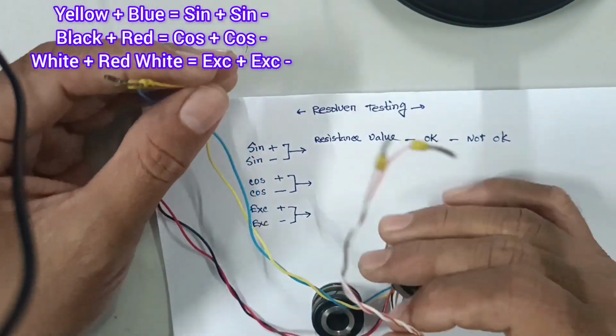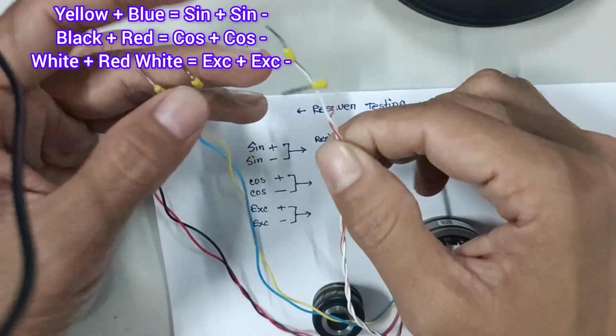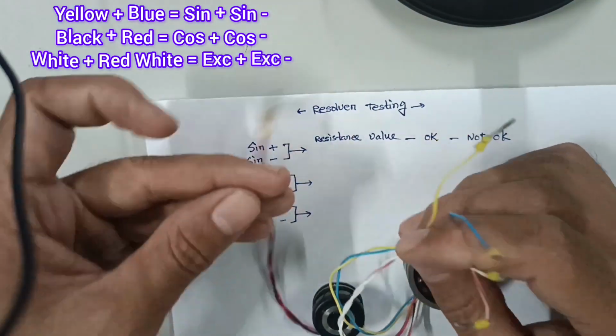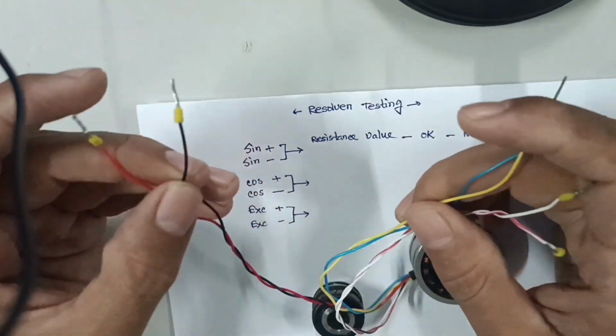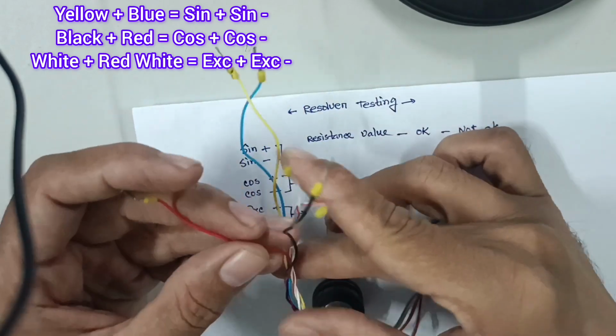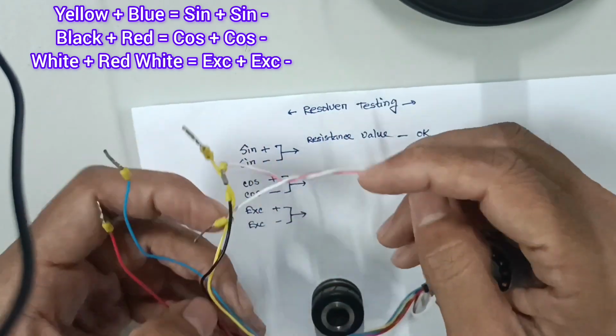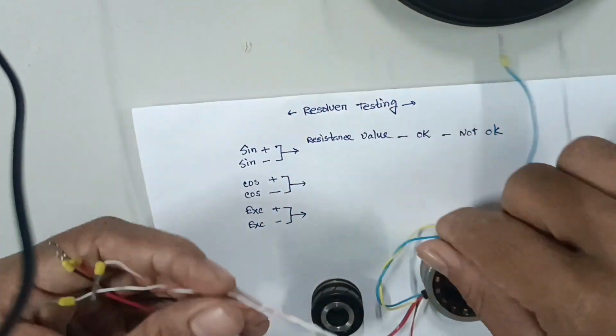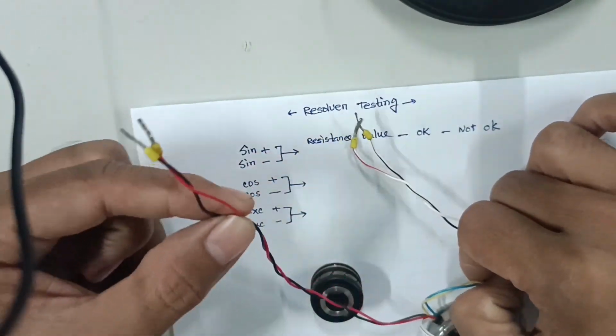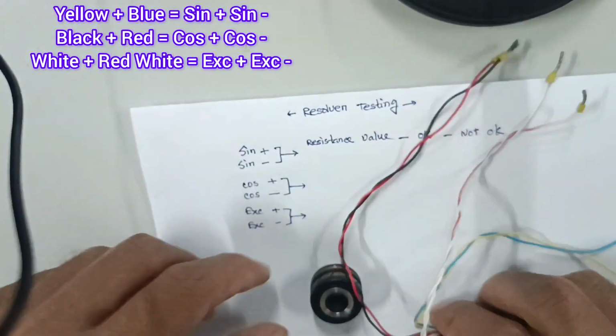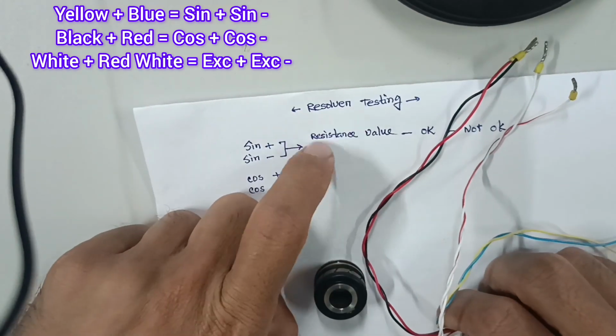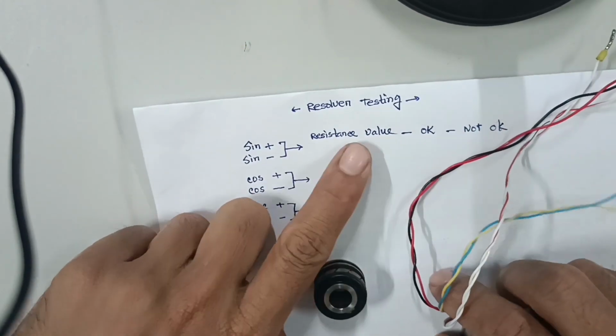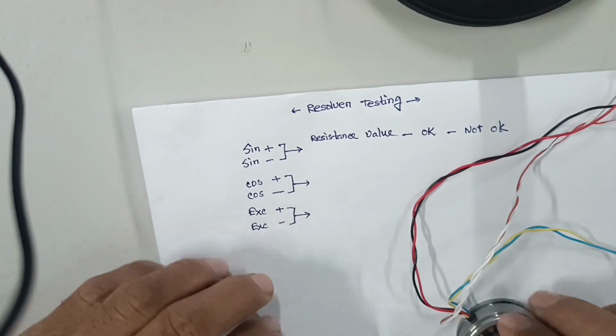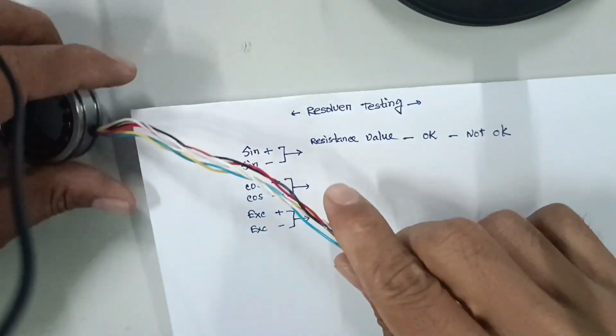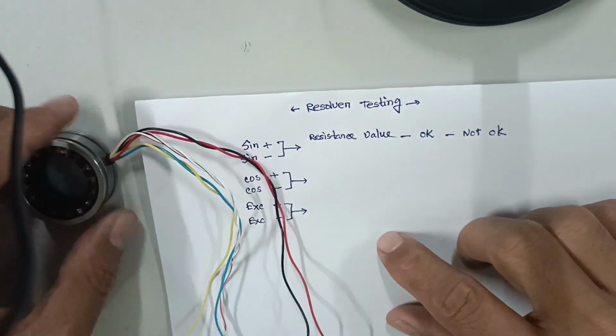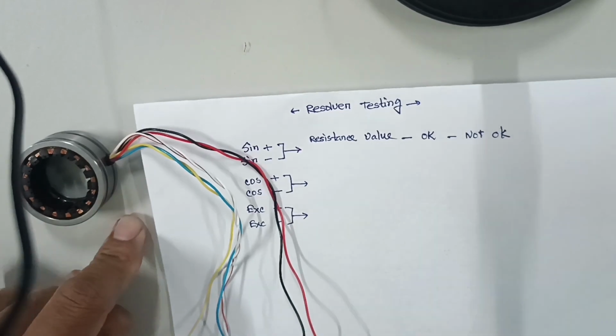First of all, Yellow and blue is sine plus, sine minus - these are the output cables, output connections. Yellow and blue is sine plus and sine minus. Black and red is cosine plus and cosine minus. White and white-red is excitation plus and excitation minus - this is the primary coil, the excitation coil.